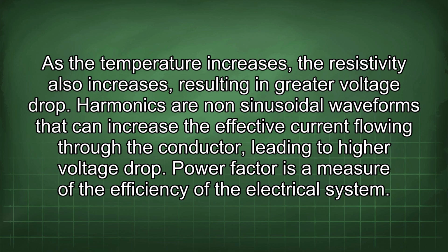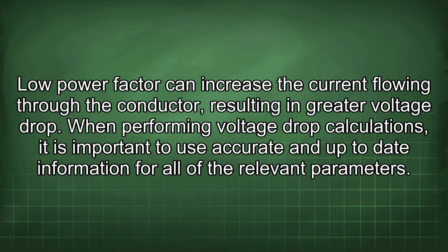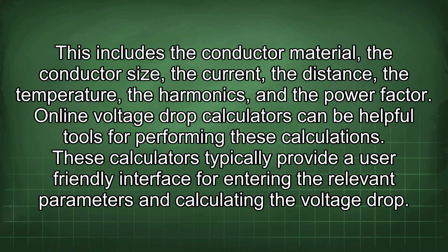Power factor is a measure of the efficiency of the electrical system. Low power factor can increase the current flowing through the conductor, resulting in greater voltage drop. When performing voltage drop calculations, it is important to use accurate and up-to-date information for all of the relevant parameters. This includes the conductor material, the conductor size, the current, the distance, the temperature, the harmonics, and the power factor.